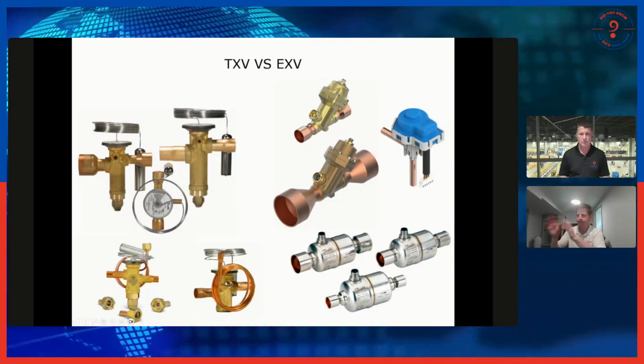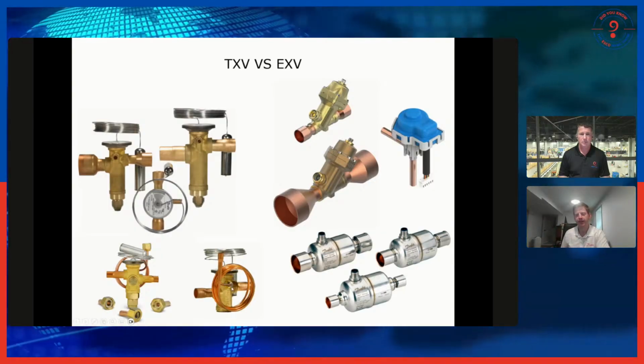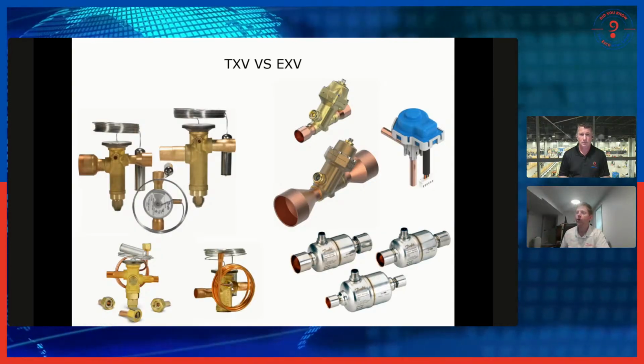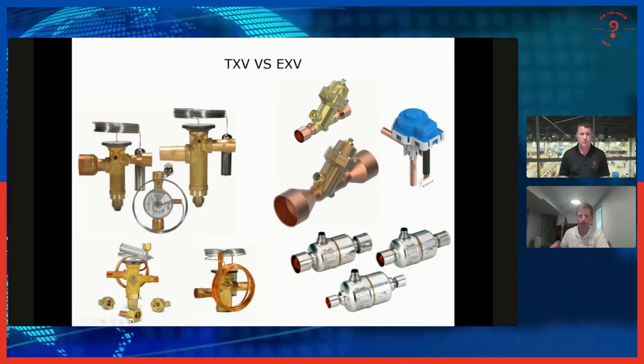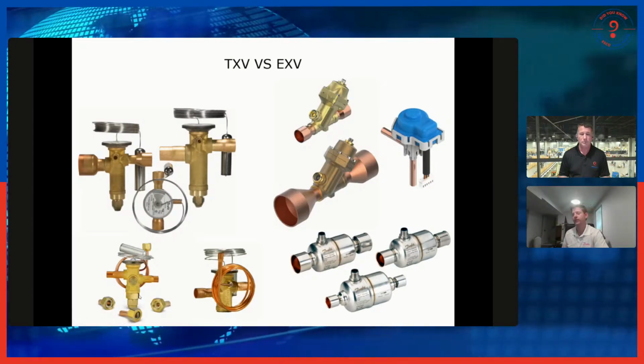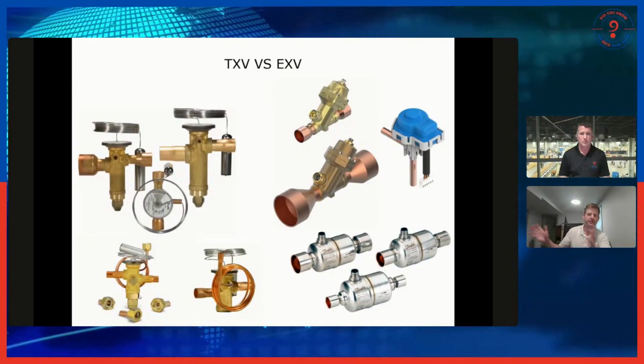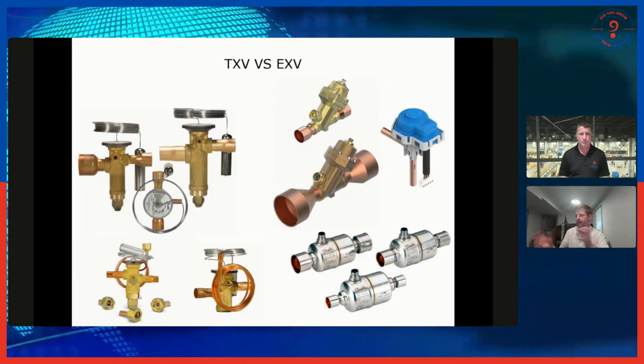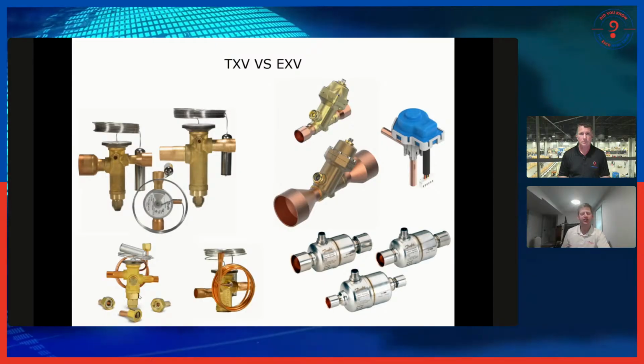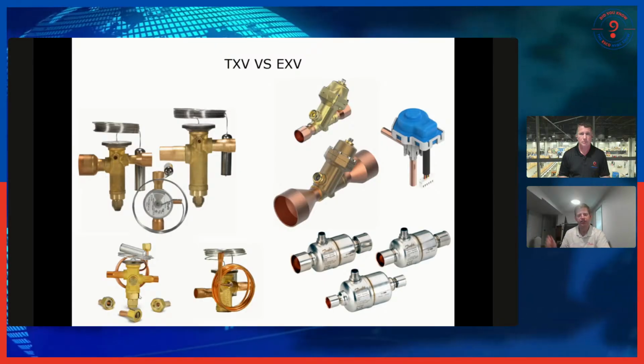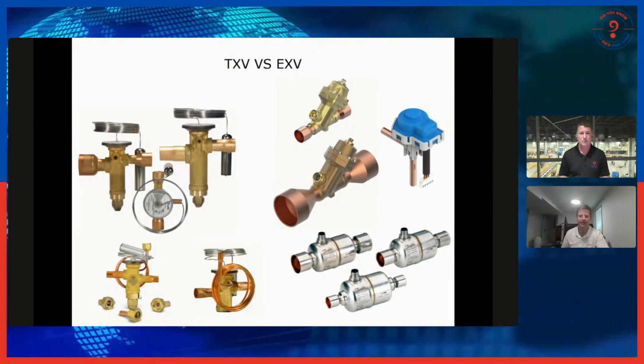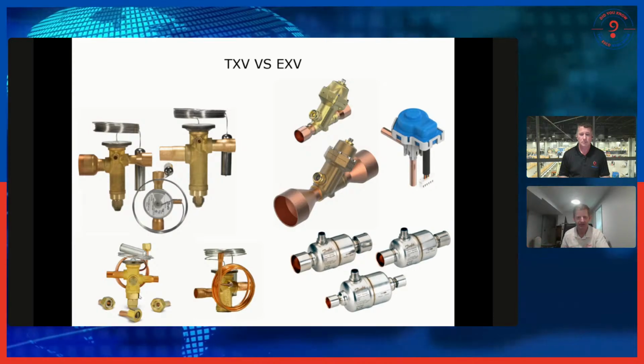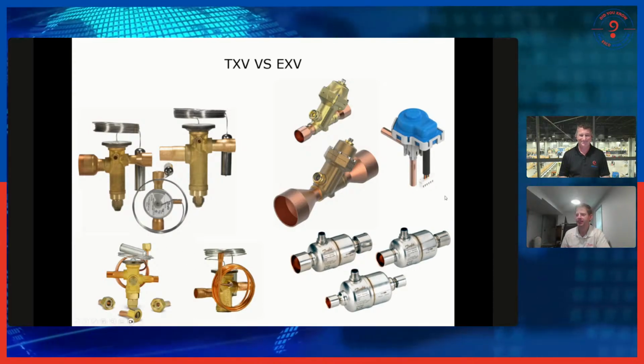But whether it's a non-adjustable valve that is coming from the factory with its own setting, or an adjustable valve that you're able to dial in yourself on a piece of equipment, once you've set it, it's set. Now it's got its superheat setting. It can't do anything else. I guess in theory, someone could have you come back each season and adjust it, but that just doesn't happen. Right, that's the difference between the two.